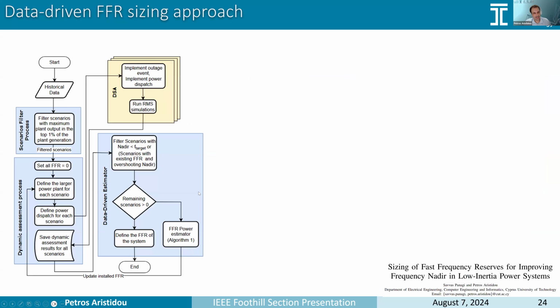Now, this is the last part that I'm going to talk about. We had a project with the transmission system operator. They asked us to provide the fast frequency reserves required in order to ensure that the system is secure during different operating conditions. This was some work from my PhD student, Savas, where we used historical data from the last 4 years, and we selected the scenarios that had problems with post-fault nadir. Then this algorithm was used to size the necessary fast frequency reserves needed to fix this problem.